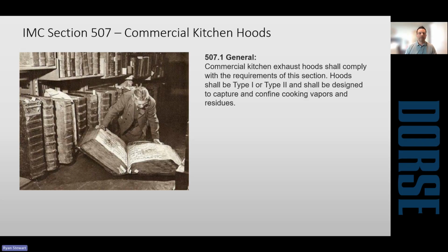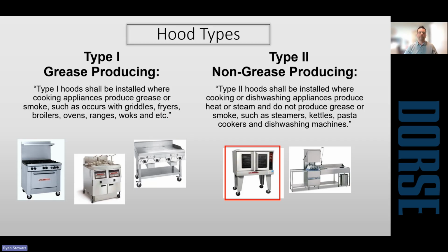So hoods are going to fall into Chapter 507 of the International Mechanical Code, and there's going to be two types of hoods. Type 1 is going to be for grease-producing appliances, where the cooking process produces a grease-laden vapor or smoke. Some of those appliances are going to be griddles, fryers, ranges, broilers, woks, etc. And then there's Type 2, and those are going to be for heat and steam, where the cooking process produces no grease-laden vapor or smoke. So that's going to be your dish hoods, steamers, kettles, pasta cookers.